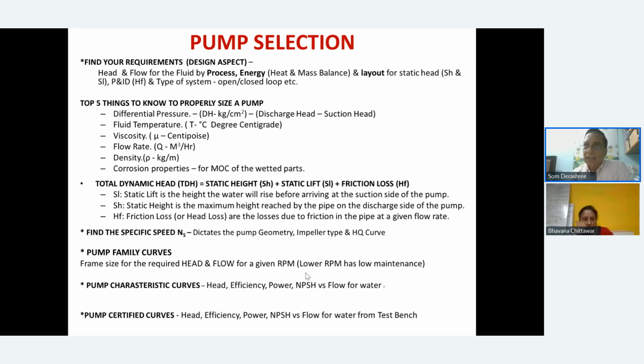Of course, if you need a different RPM, then you'll have to have either a gear arrangement or a pulley arrangement. But these all lead to losses. The preferred thing is to have a direct coupling or a direct connection to the motor. So the motor will go either 3000 RPM, because it is 120 f by P. If you take a 2-pole motor, it is 3000, then a 4-pole is 1500, then you have 1750. Like that, you will have to arrive at the RPM.